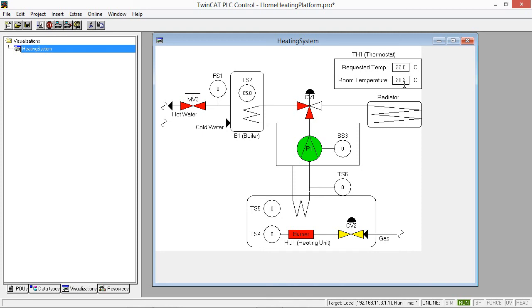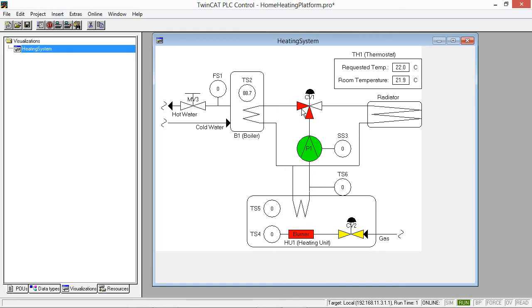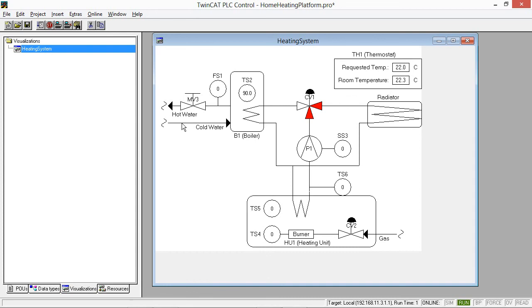But if I put more room temperature, now also both the room and boiler is heated. But if I close the hot water tap, now the temperature starts to increase in the boiler. And when it reaches the 90 degrees, then it should stop the boiler and the burner. Like this. But now the pump and boiler went again because the room temperature decreased.